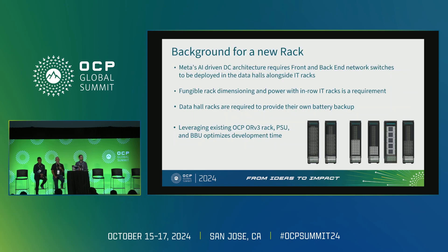For the background on the new rack, we really have to talk about the existing DC Type 1 network for Meta. That's basically your H buildings — largely front-end production and some AI ML and some storage. The network rooms were dedicated, meaning your data hall was completely separate from your MDF and your BDF. The network racks in those rooms were four-post, 19-inch, AC power — no in-rack battery at all — and they were tied into a building-level UPS.